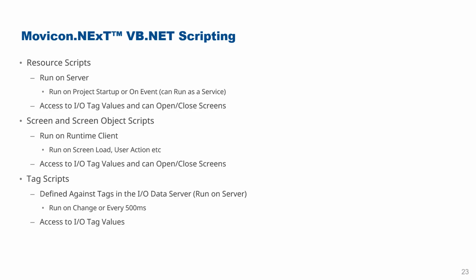Now the final option here is tag scripts. Tag scripts are defined against tags in the IO data server. So they do run on the server, but they only run on change, or you can have them running every 500 milliseconds. So there's an option for running on a regular basis, but it's on a timed basis, about every half a second.